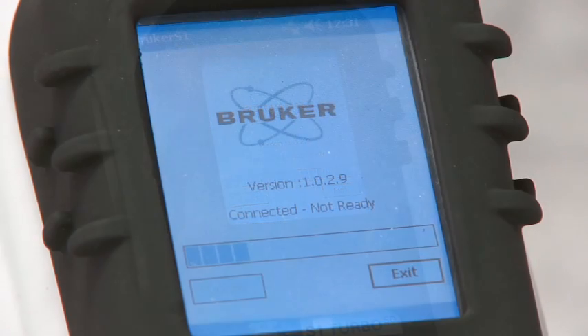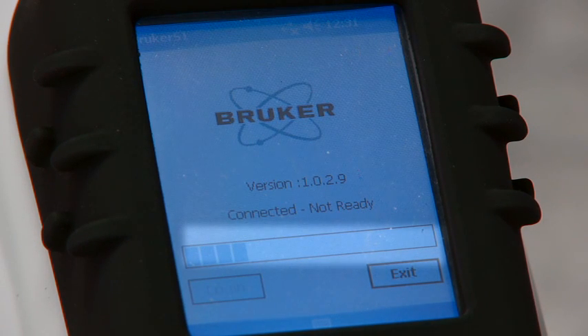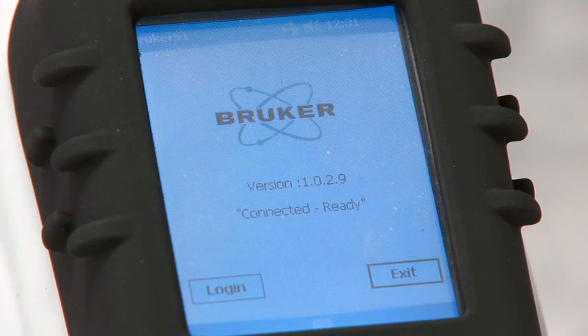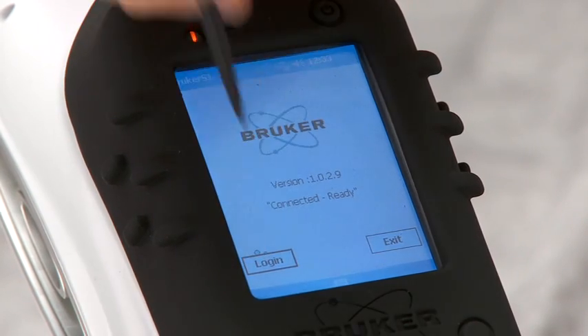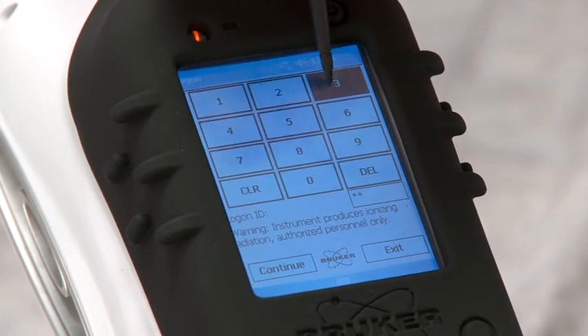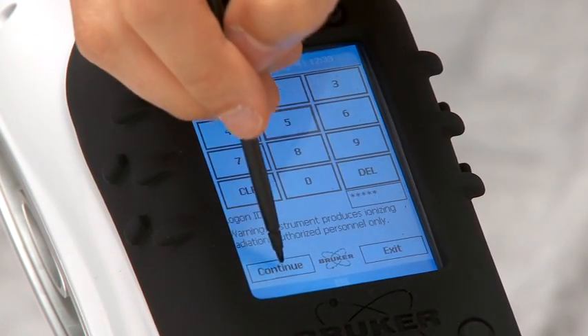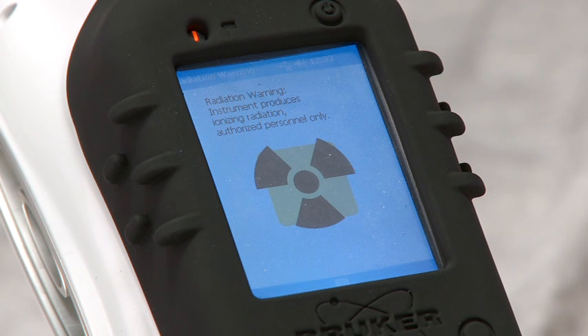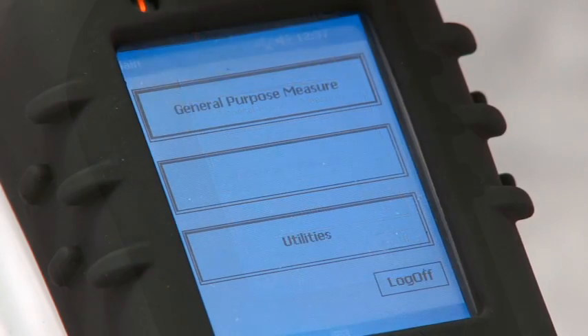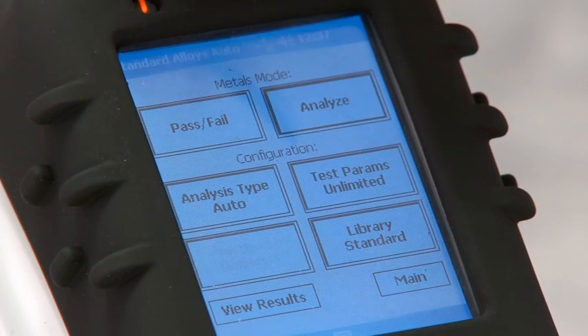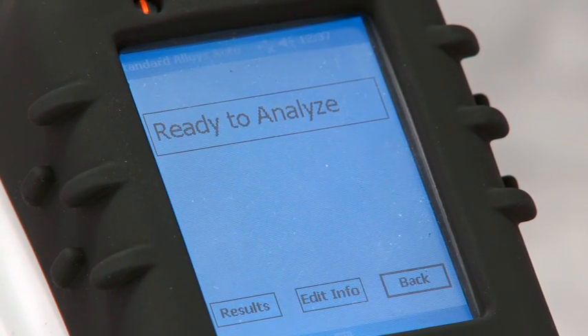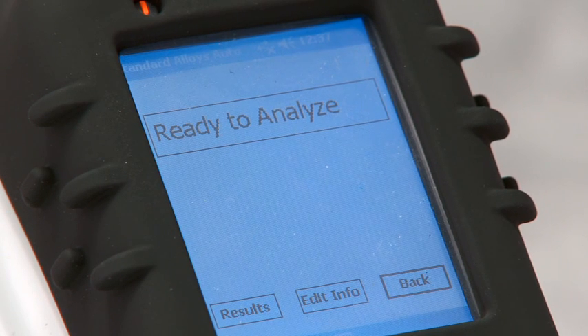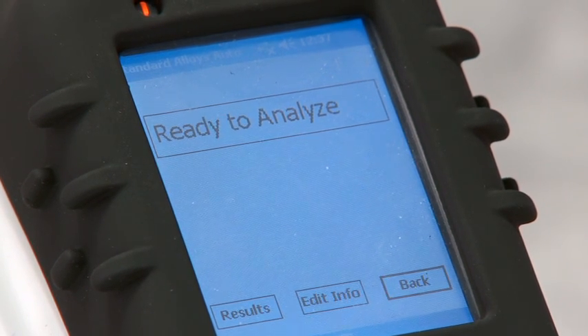Once the software is activated, the PDA and analyzer will connect. This is indicated on the screen. The status bar will generally shrink, giving the user the ability to log on. Tap the Log On box and enter the password 12345 and tap Continue. At this time, a radiation safety warning will be shown for about 15 seconds. If the instrument does not go directly to the Ready to Analyze screen, tap the General Purpose Measurement button to place the analyzer in the universal mode for taking general alloy measurements. After that, the analyzer goes to the Ready to Analyze screen. At this time, you are ready to make a measurement.